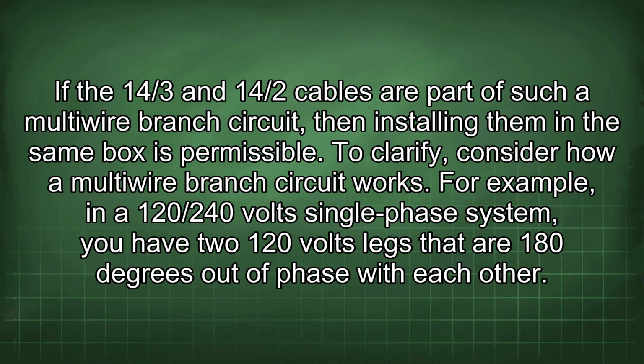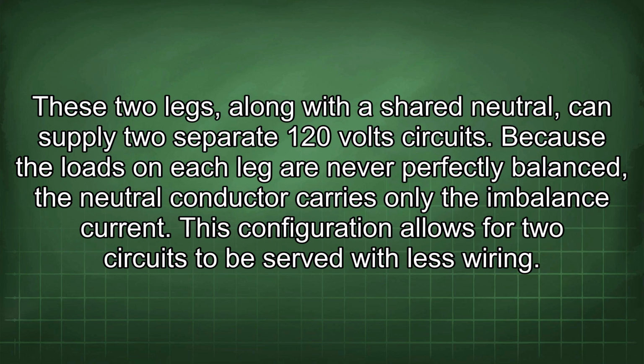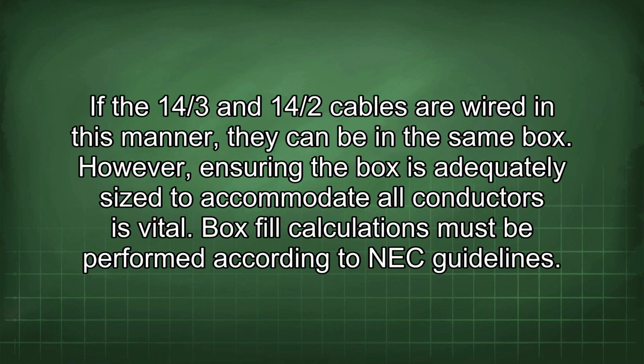For example, in a 120/240 volt single-phase system, you have 2 120 volt legs that are 180 degrees out of phase with each other. These 2 legs, along with a shared neutral, can supply 2 separate 120 volt circuits. Because the loads on each leg are never perfectly balanced, the neutral conductor carries only the imbalanced current. This configuration allows for 2 circuits to be served with less wiring. If the 14/3 and 14/2 cables are wired in this manner, they can be in the same box.